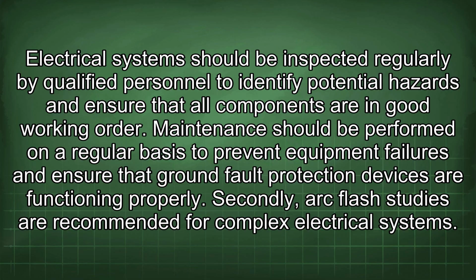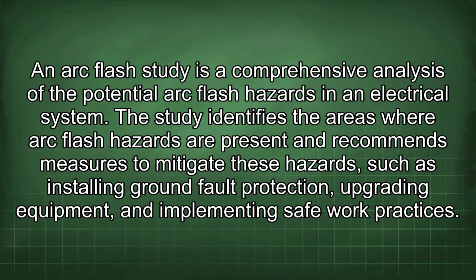Secondly, arc flash studies are recommended for complex electrical systems. An arc flash study is a comprehensive analysis of the potential arc flash hazards in an electrical system. The study identifies the areas where arc flash hazards are present and recommends measures to mitigate these hazards, such as installing ground fault protection, upgrading equipment, and implementing safe work practices.